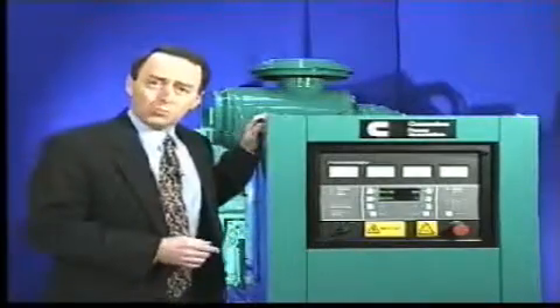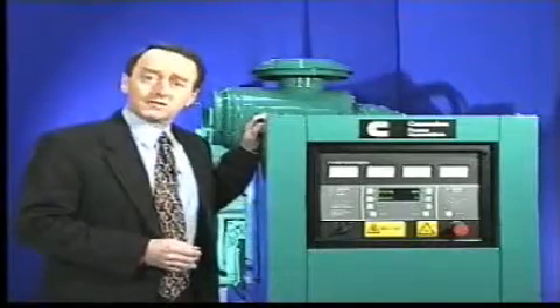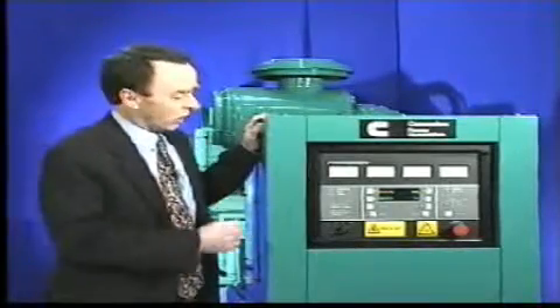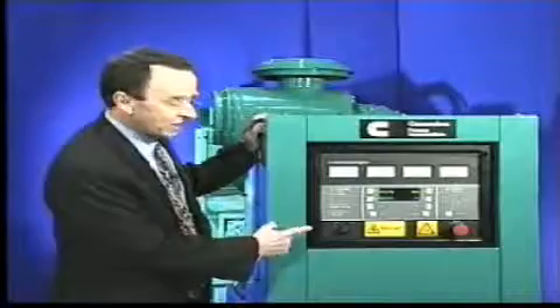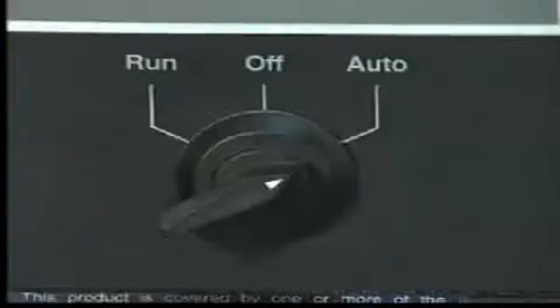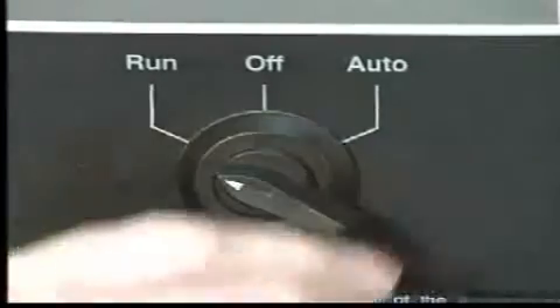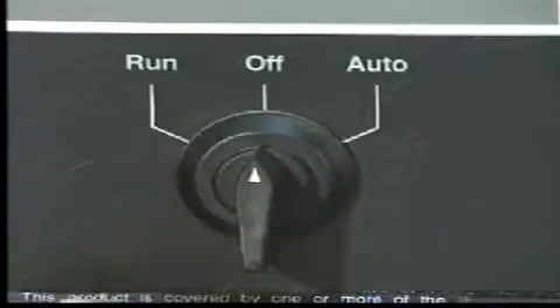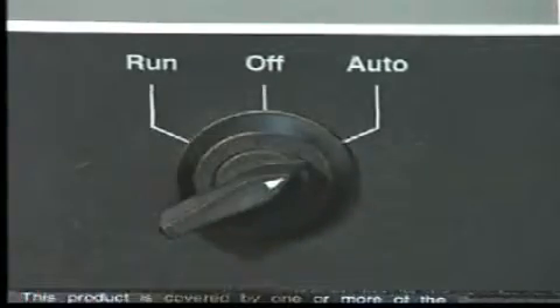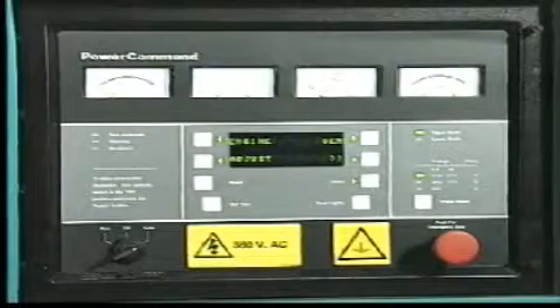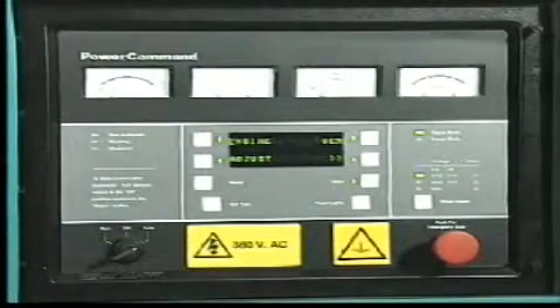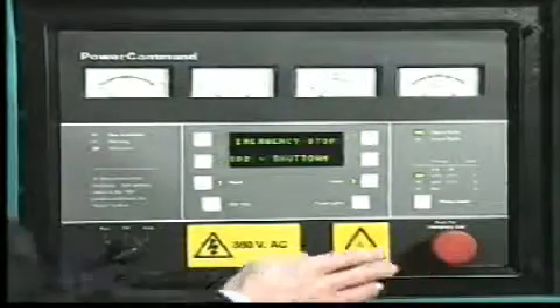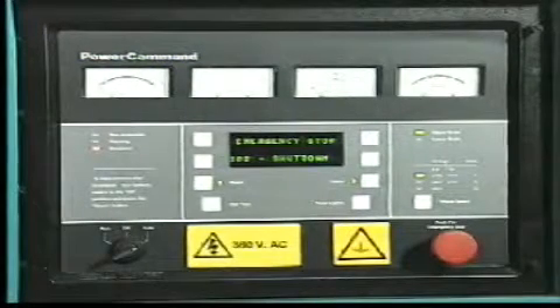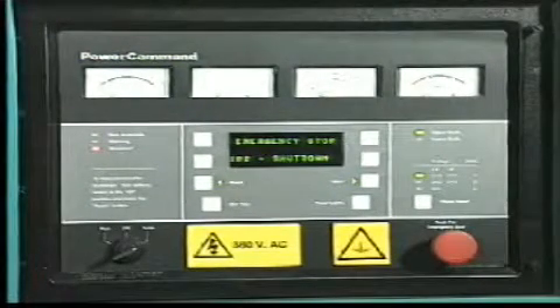There's just one control panel to deal with, not a whole squad of sections and modules. No rows of knobs and trimmers, just one switch which requires a hand turn. Run for manual start, off, and auto for remote automatic transfer switch connection. And a prominently placed emergency stop button. When it's pushed in, the generator set is immediately shut down and locked out until the unit is properly reset.